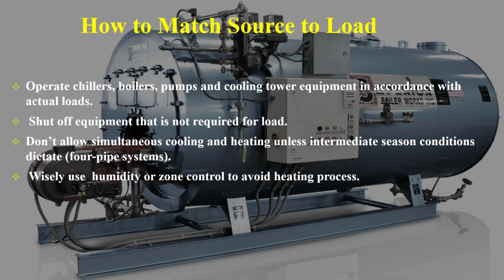How to match source to load. Operate chillers, boilers, pumps and cooling tower equipment in accordance with actual loads. This assumes that necessary control devices are in place but not tuned as required. Shut off equipment that is not required for the load by automation tools. Don't allow simultaneous cooling and heating unless intermediate season conditions dictate, four-pipe systems. Wisely use humidity or zone control to avoid a reheating process.